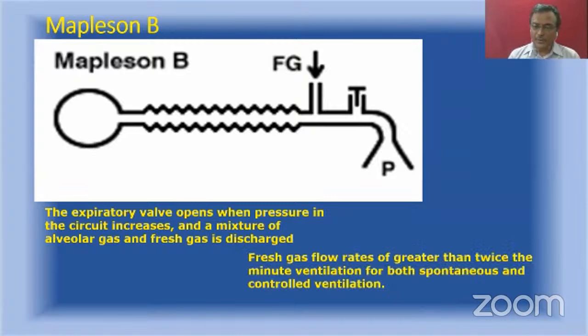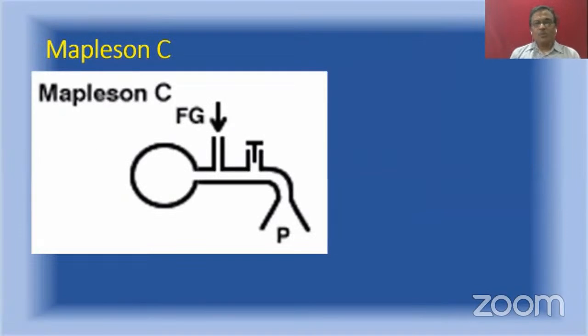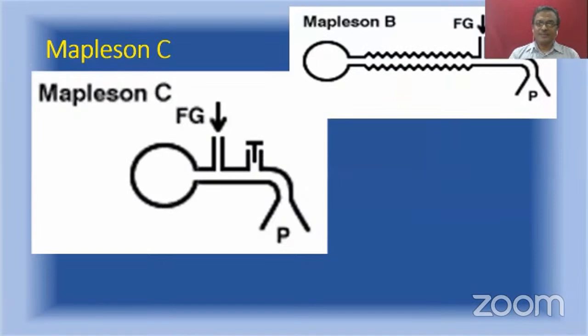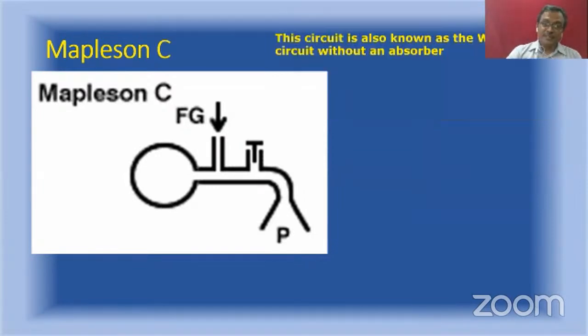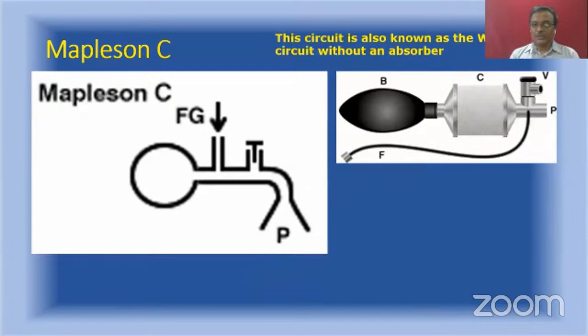So fresh gas flow requirement is around twice minute ventilation. It is applicable for both spontaneous and controlled ventilation. There is no difference in fresh gas flow, and nowadays, Mapleson B is an obsolete circuit. Nobody is using it. Now we move on to Mapleson C. In what way is this different from Mapleson B? Just compare. See, there is a breathing tube in the Mapleson B, which is absent in Mapleson C. So that is the only difference between Mapleson C and Mapleson B. And Mapleson C is also known as the Waters circuit without an absorber. I hope all of you remember the Waters circuit, which is a to-and-fro circuit with carbon dioxide absorption. And when you remove the absorbent or the canister absorber, it will become Mapleson C.